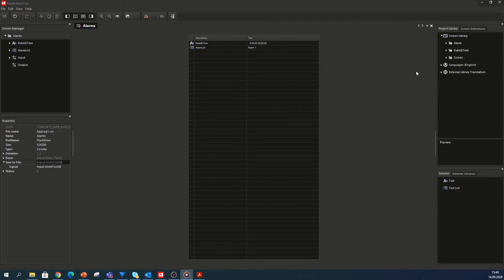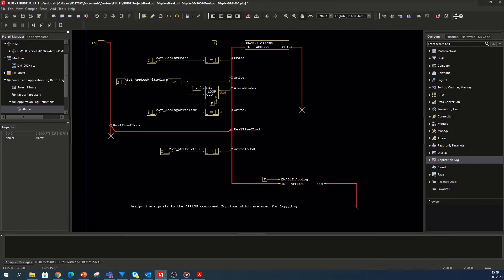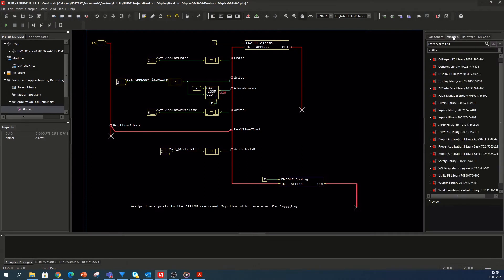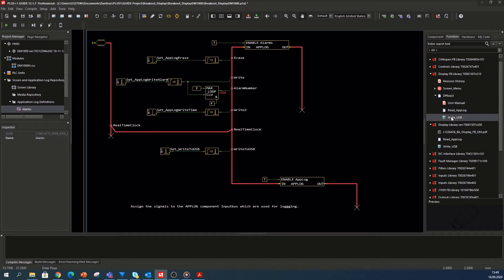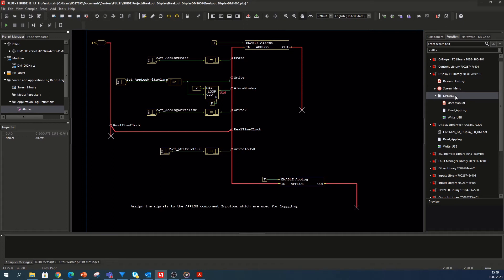Another possibility to access and read the application log data and store them on a USB stick is via the display library. This feature can be used on controllers where the save to file property is not available. The display library and display function block library provide two function blocks which help to easily read out the application log data and store these data on a USB stick. They have been developed for the DP 600 display release where this functionality was added to the HWD first. That's why the DP 600 is mentioned in the manual, but the functionality can also be used on newer controllers equipped with the USB host.